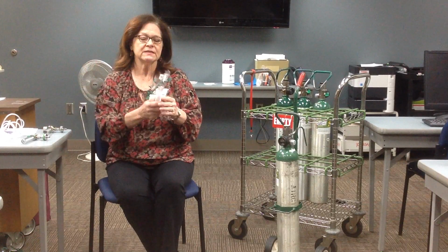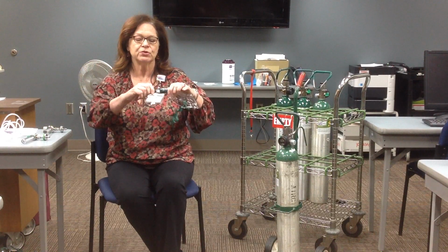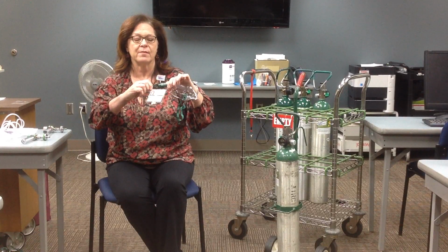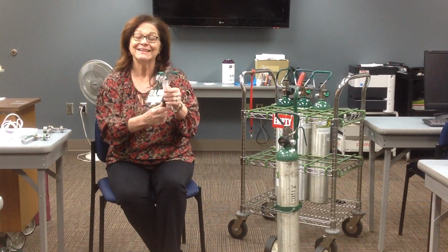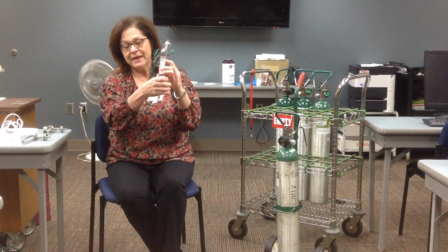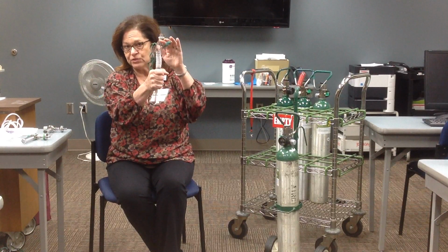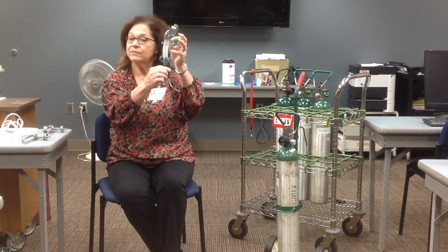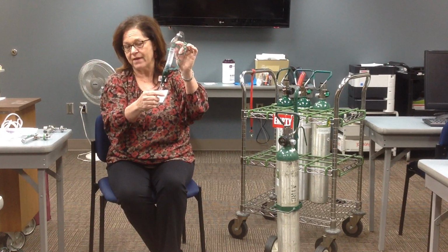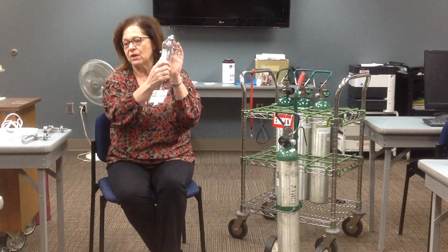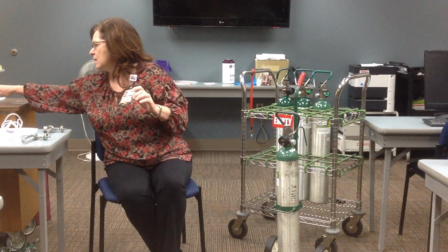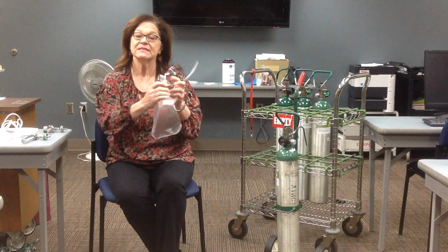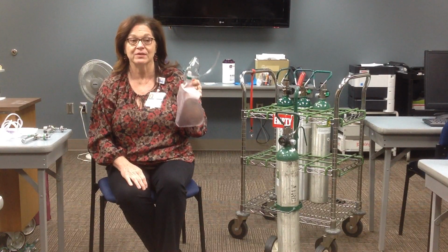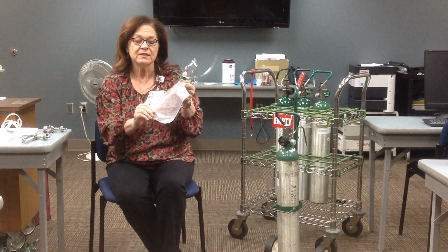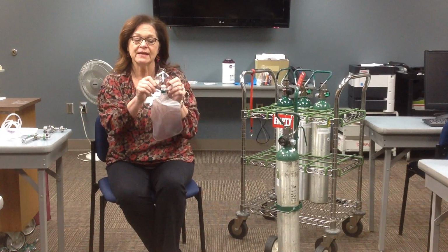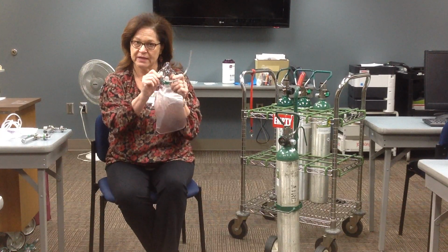The Venti mask is a great tool. It has the venturi where you dial in your oxygen level from 24 to 50%, and it's still a great tool. However, if the patient is holding their hand over that venturi device and obstructing the venturi, it can change the actual FiO2, or if it's covered up, so we stopped using that one. Non-rebreather. Everybody comes into the emergency room on a non-rebreather via ambulance, right? We quit using this because if you turn it down too low, the patient can also rebreathe their CO2.